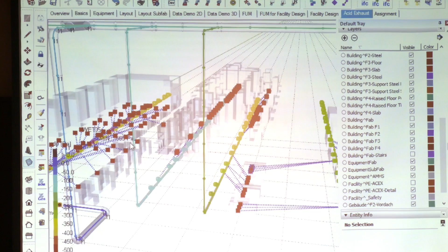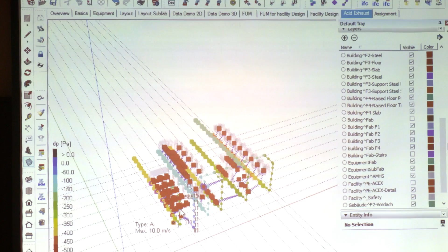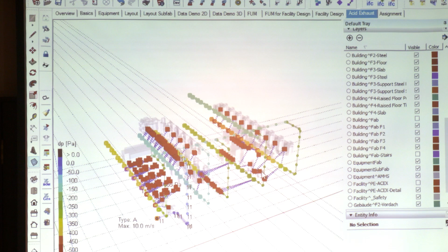And we can answer our client in this case: he doesn't have to be concerned about the system, it will work perfectly with a quite low pressure loss. The minimum point is shown here, it's 565 pascals, which is very good for this infrastructure. Okay, so this is our little pressure calculation tool, and now the question is how to pass on the geometries we've created.